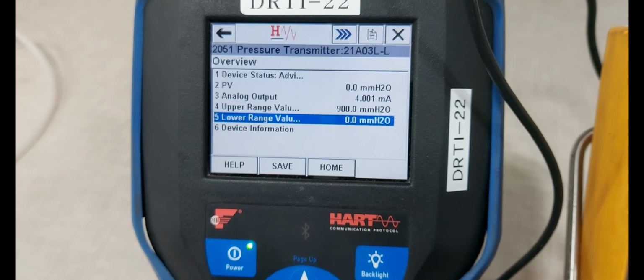Next we are checking the 5-point verification. Close the vent valve, pressure calibrator. Next we are applying the pressure. Now milliamps also vary. Now 222.5 mmH2O almost reached and steady condition. Also showing 225 mmH2O, 25.02%. Now output is showing 7.999 milliamps.